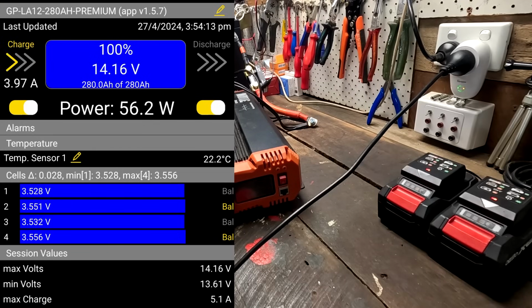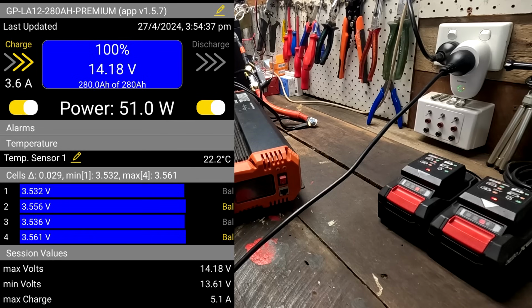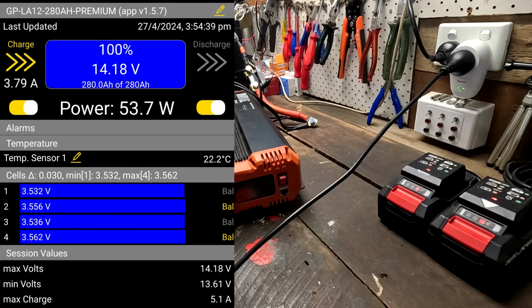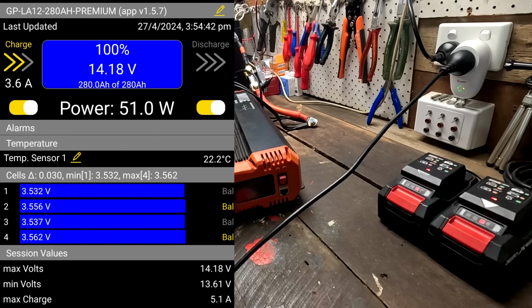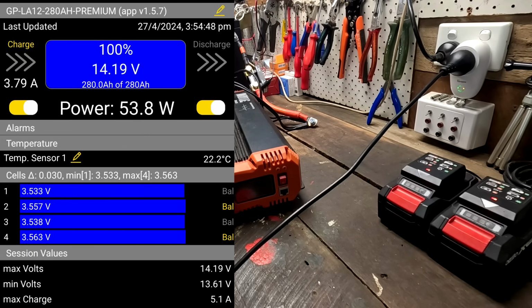So we now have reached a peak voltage of 14.16 volts. Deviation has increased to 30 millivolt now, which is normal. But 14.2 volts would probably be a voltage which most people charge to. So there's no issue with the battery itself - there's no peaking cell, no runaway, and no overvoltage protection happening at this voltage.